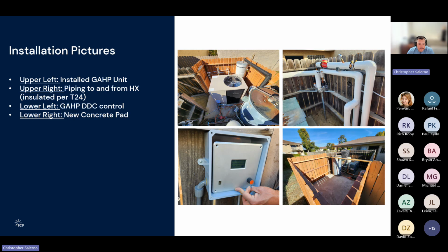So you can see here that the system is being integrated, and then the piping here is how we integrated the heat exchanger to preheat the cold city water going into the system. Following the red dot, the cold city water will come in. Actually, there's a pipe behind that. It'll come in, you can see right there, and then it'll come out heated and go back to the boilers. This is the water glycol mix that's going to and from the gas absorption heat pump. And so you can see here we have our flow meter. We have a pressure gauge to maintain. We have a circuit setter here to maintain equal flow to both systems, as you want to have equal flow to both systems, and then mass balance the flow on the heat exchanger to maximize the efficiency of the heat exchangers.